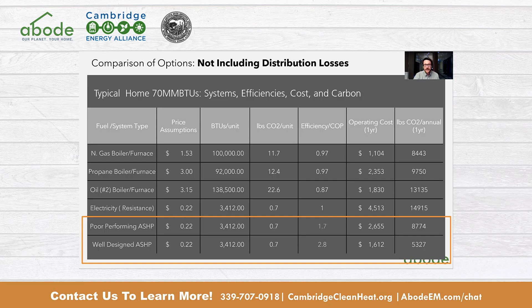I'm not showing the distribution losses of any of the gas, oil, or propane systems. For a furnace, that could be 20% or 30%, or with airtight ductwork, as little as 5% losses. But for a steam system, about 40% of the energy is lost through the distribution, through all the steel and cast iron, heating it all up to 212 degrees. Here's what the numbers look like: this is the equivalent of about 600 gallons of oil, or 70 million BTUs, over the course of the year.